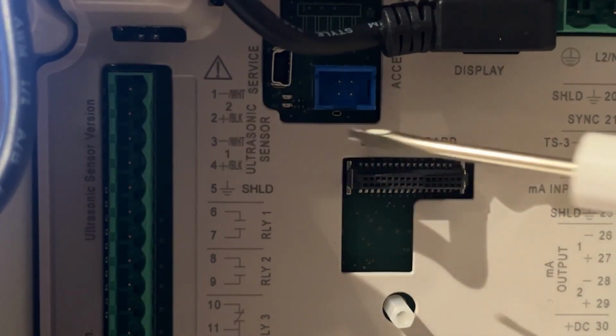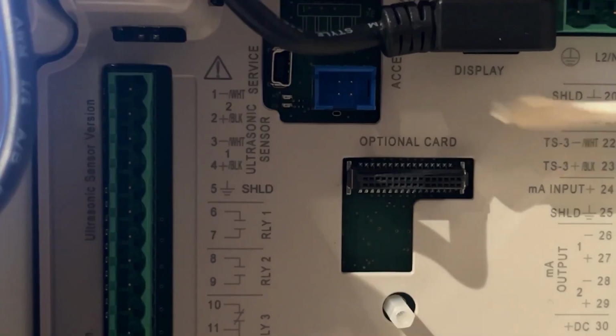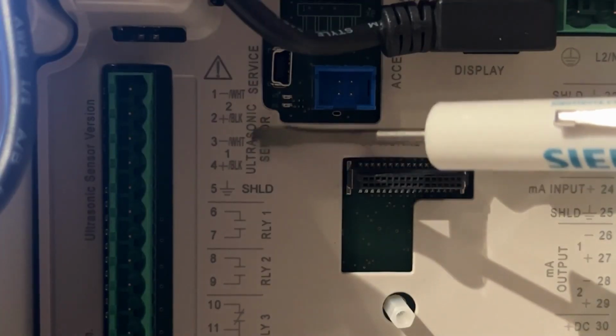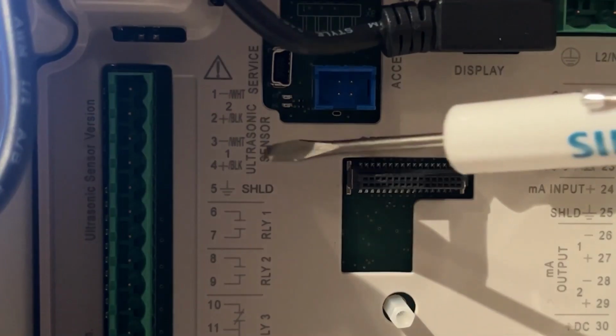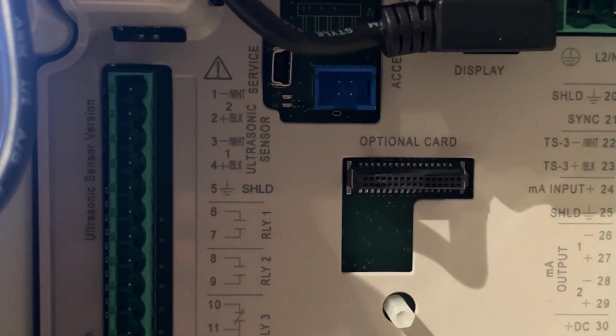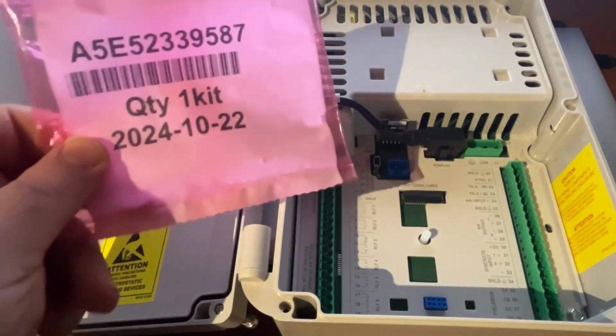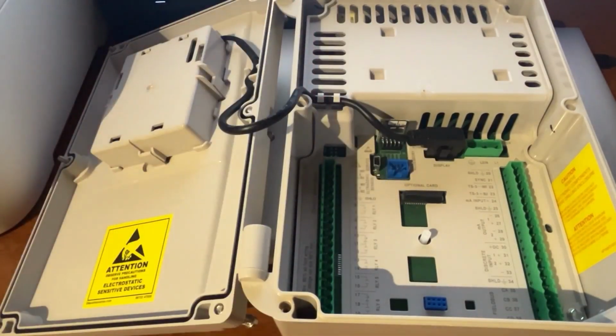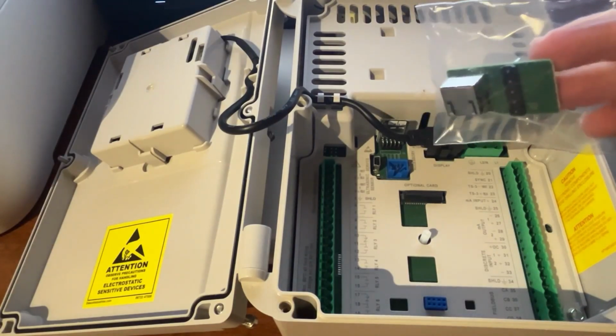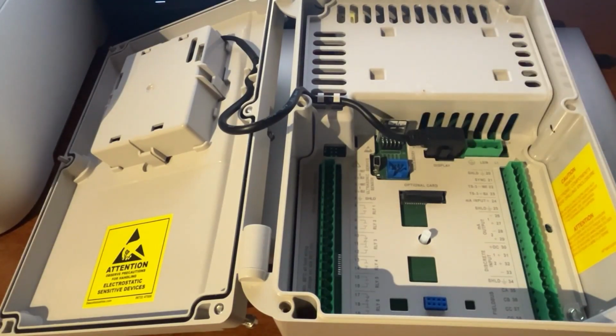positive and negative symbols, as well as the color of the wire and another identifier of what type of sensor input it should be. So in this case, it's an ultrasonic sensor. On a milliamp part or radar variant, it would say milliamp input there as well. The device comes with this kit of terminal blocks, and because we've ordered an industrial Ethernet type communications card, it also comes with this Ethernet adapter, which we'll also install.